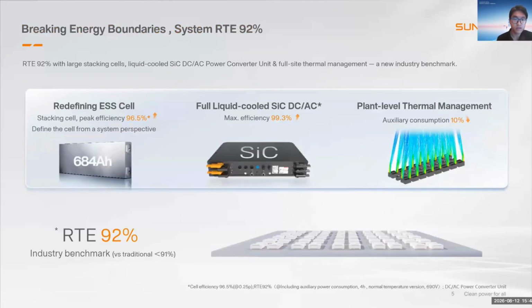So this page is about the system RTE. For our Power 3, we have three main technical progresses. The first is we redefine the battery cell from 314 ampere-hour to 684 ampere-hour, with stacking technology, and the peak efficiency can achieve 96.5%. The second point is we use the fully liquid-cooled silicon carbide PCS with the maximum efficiency of more than 99.3%. And the third point is we have plant-level thermal management, which can reduce the auxiliary power by 10%. So thanks to this technical progress, the system RTE can achieve 92% at the LV side. That means we can have more useful capacity and more revenue.